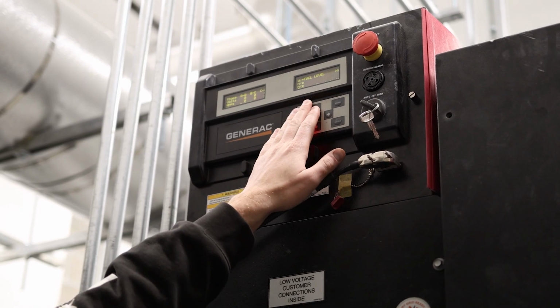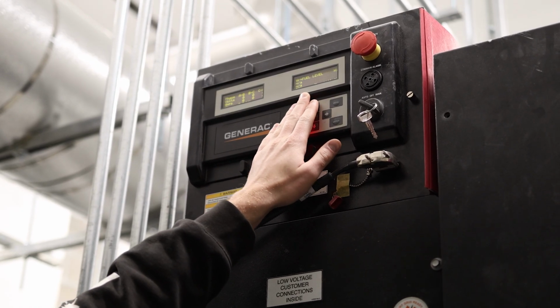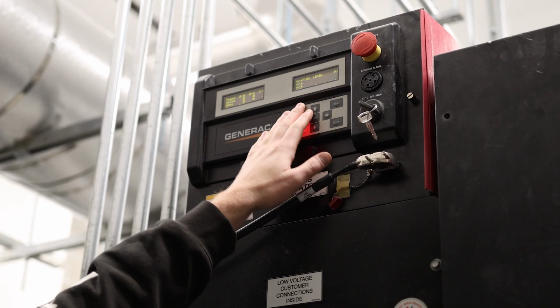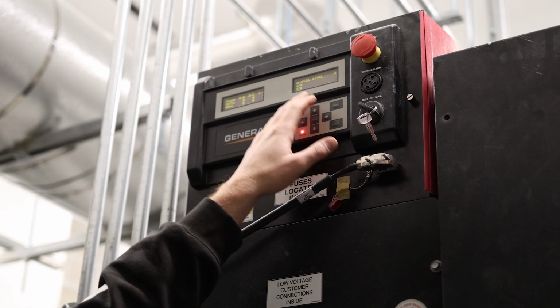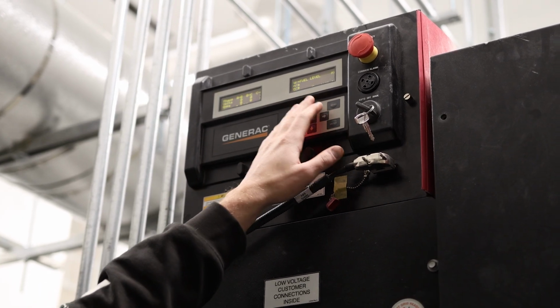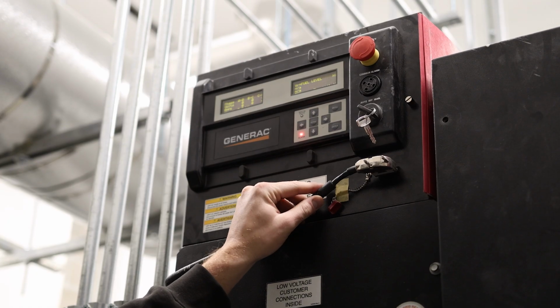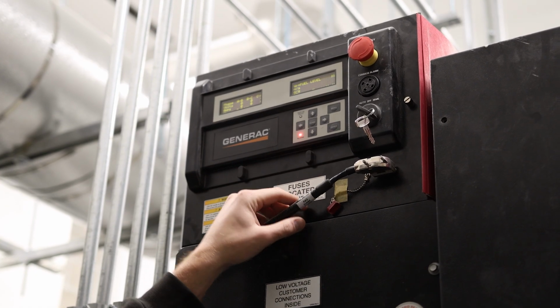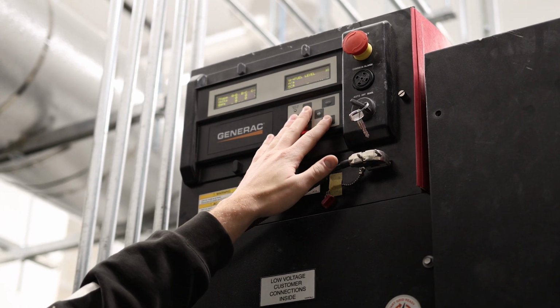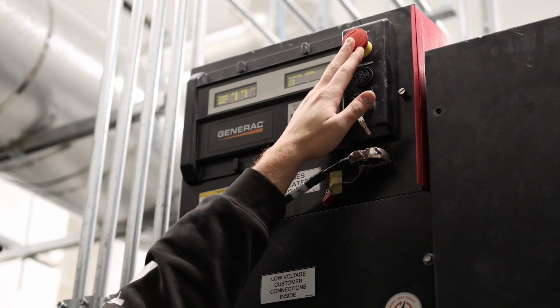On the right display, it's currently showing we're in an alarm. Whenever an alarm happens on the unit, the right display will change to the alarm page immediately. The alarm currently is warning for high fuel level because we're above that threshold. If it were to throw an alarm, you might have to go reset the fire alarm panel here.